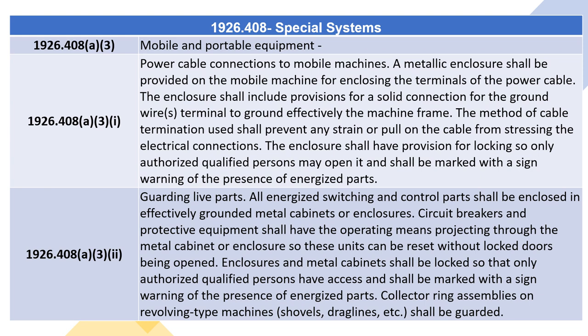1926.408(A)(3)(ii) — Guarding Live Parts. All energized switching and control parts shall be enclosed in effectively grounded metal cabinets or enclosures. Circuit breakers and protective equipment shall have the operating means projecting through the metal cabinet or enclosure so these units can be reset without locked doors being opened. Enclosures and metal cabinets shall be locked so that only authorized qualified persons have access and shall be marked with a sign warning of the presence of energized parts. Collector ring assemblies on revolving type machines — shovels, drag lines, etc. — shall be guarded.